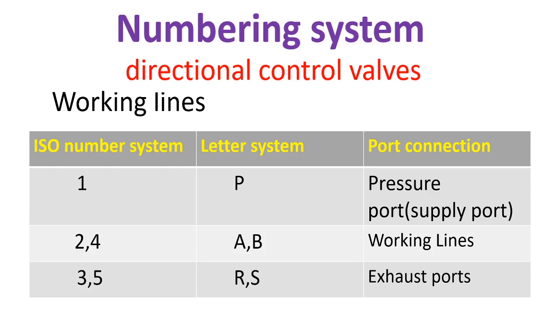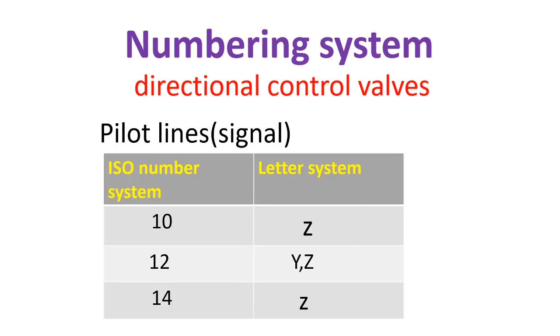For number two and four or A or B, that is working lines. For number three and five or R and S, that is exhaust ports. And for pilot lines or signal, 10 is equivalent to Z, 12 is equivalent to Y or Z, 14 is equivalent to Z.